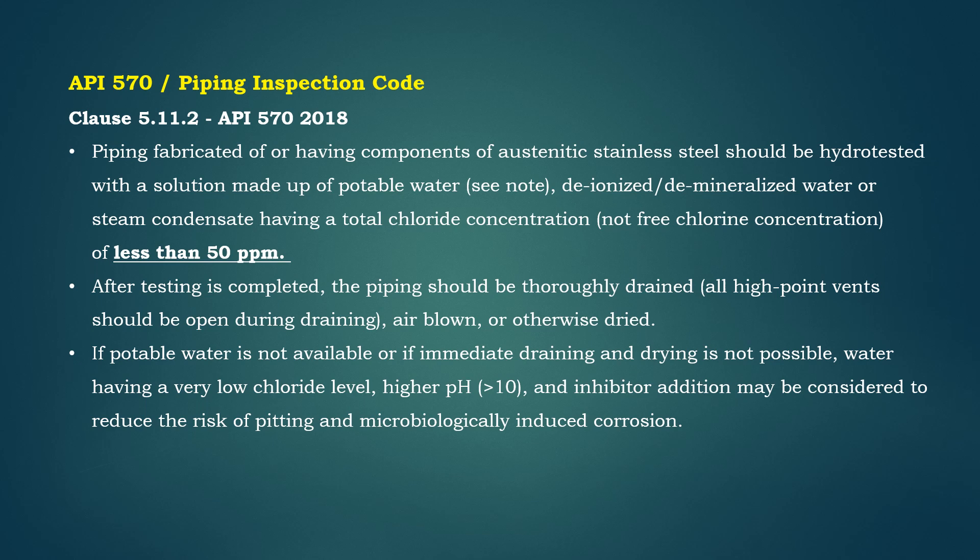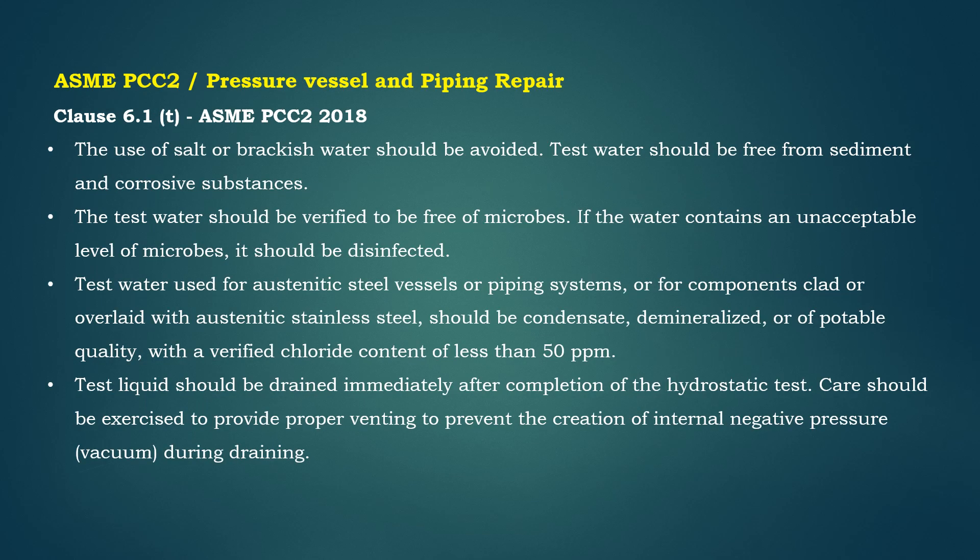If potable water is not available, or if immediate draining and drying is not possible, water having a very low chloride level, higher pH, and inhibitor addition may be considered to reduce the risk of pitting and microbiologically induced corrosion. The use of salt or brackish water should be avoided.